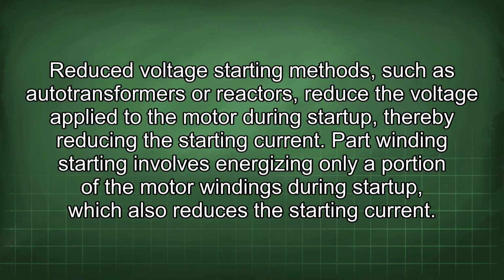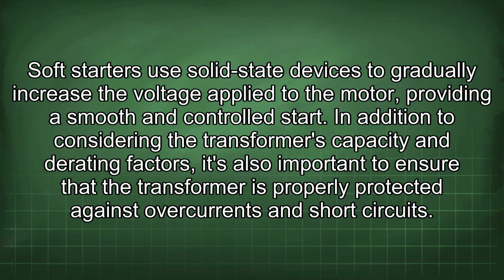Reduced voltage starting methods, such as autotransformers or reactors, reduce the voltage applied to the motor during startup, thereby reducing the starting current. Part winding starting involves energizing only a portion of the motor windings during startup, which also reduces the starting current. Soft starters use solid-state devices to gradually increase the voltage applied to the motor, providing a smooth and controlled start. In addition to considering the transformer's capacity and derating factors, it's also important to ensure that the transformer is properly protected against overcurrents and short circuits.